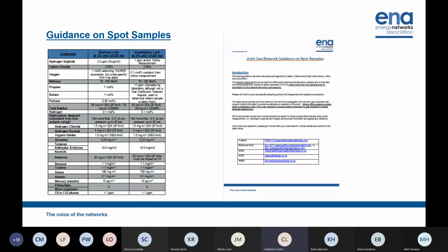But this sets out the spot samples that are set out by your DN. They will agree with you a time frame for spot samples, whether that be monthly, 3 monthly, 6 monthly. The levels in the center column are the limits that you're allowed within the gas safety management regulations, and the column on the right is the limits where we would expect you to investigate why the levels are so close to the levels in GSMR. If they go over, then we want an inspection to be carried out, or if they're getting close, so we can stop them going over. We don't want them to be a breach.